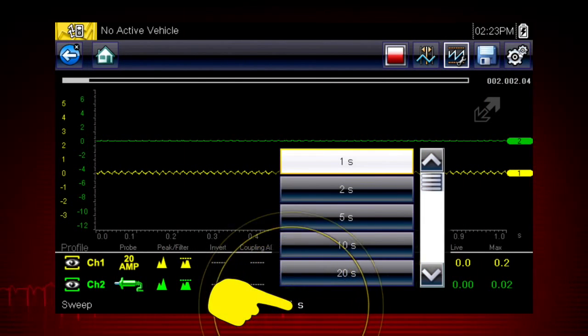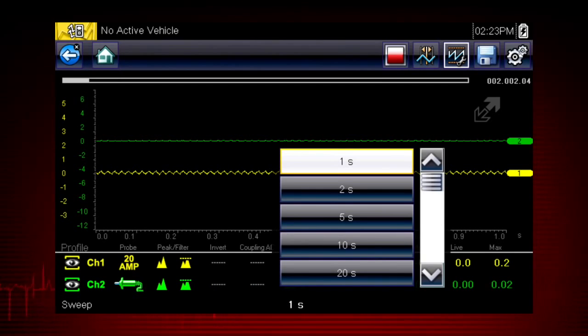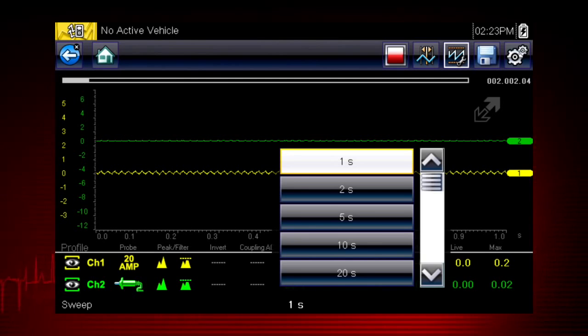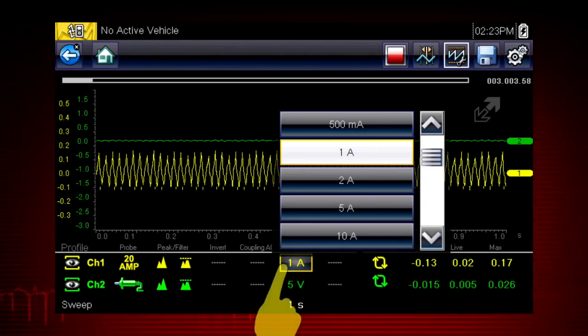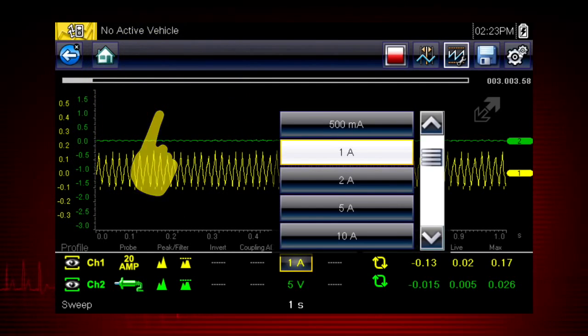Easily change the time scale or sweep using the sweep menu. You can set the total time it takes for the data to fill the screen, anywhere from 1 to 20 seconds in meter mode and as short as 50 microseconds in lab scope mode. Touch the scale value to change it anytime with this pop-up menu. After making a menu selection, simply touch a blank spot on the screen to hide the menu.